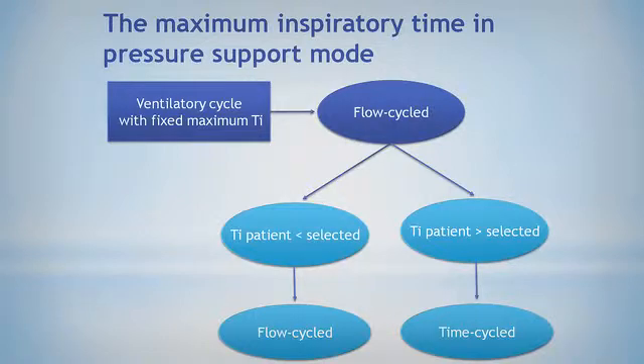On the other side, we also have the possibility of selecting a maximum inspiratory time. In this situation, the algorithm of the ventilator operates as follows: if the inspiratory time of the patient's breath is shorter than the selected maximum in the ventilator, breaths are normally flow cycled. Conversely, if the inspiratory time of the patient's breath is longer than the maximum inspiratory time selected in the ventilator, the breath is time cycled.